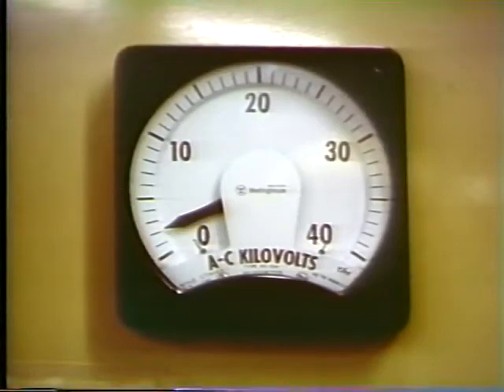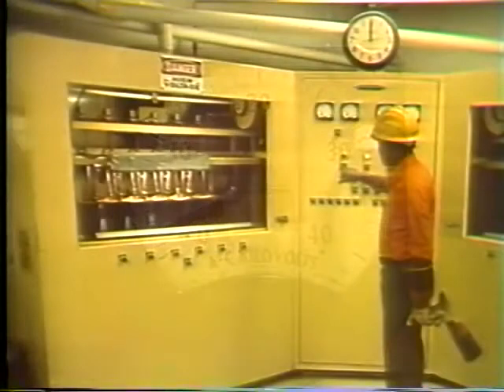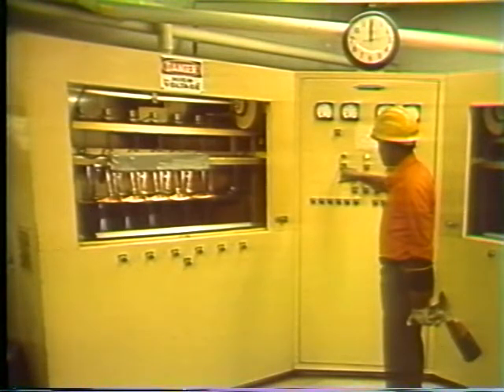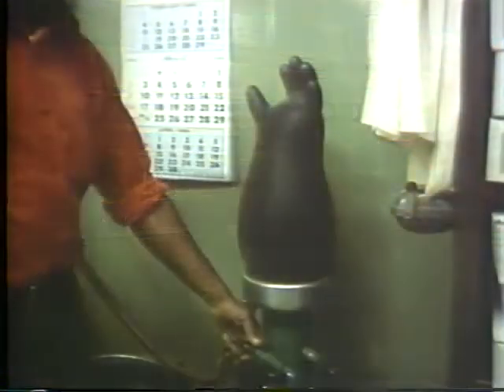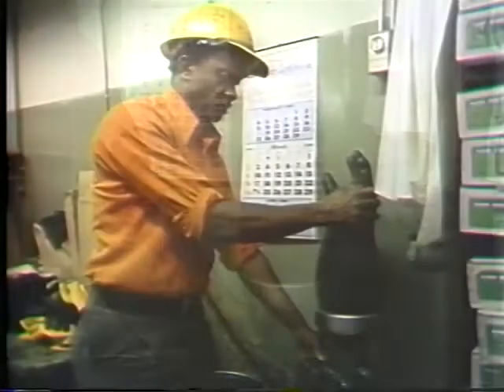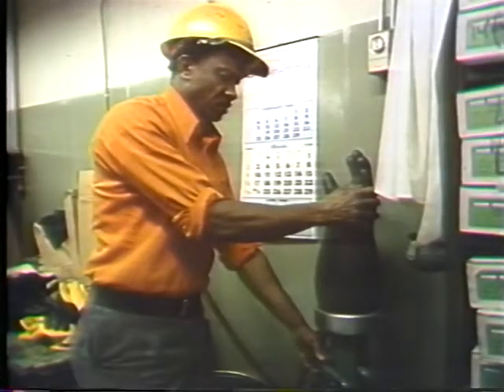But if there's even a small leak, as you can see by the small glow inside the glove, the voltage drops far below the test value. Now these gloves will have to be tested individually to find out which one caused the indication. After all the gloves have been tested electrically, they're checked visually as well. This device inflates gloves so the technician can look for punctures or weak spots that might have escaped the electrical test. Even the smallest sound of escaping air means that the glove has failed.